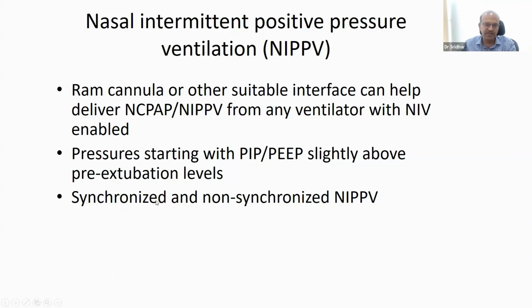In NIPPV, we have synchronized and non-synchronized. Synchronization may happen with the pressure sensor at the ventilator end. It's not the heated wire anemometer, but it's at the ventilator end, so the lag time is more. Previously, we used to have the Infant Star ventilator, which had the Graseby capsule based synchronization, but that's not used anymore. That kind of synchronization is used in biphasic CPAP as well. The Graseby capsule is used for that.